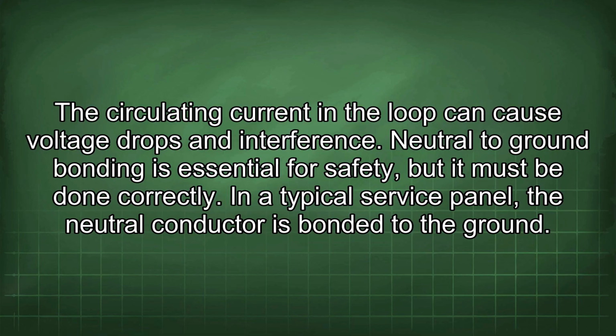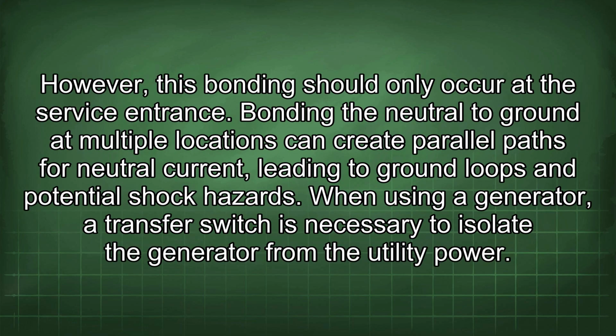Neutral to ground bonding is essential for safety, but it must be done correctly. In a typical service panel, the neutral conductor is bonded to the ground. However, this bonding should only occur at the service entrance. Bonding the neutral to ground at multiple locations can create parallel paths for neutral current, leading to ground loops and potential shock hazards.